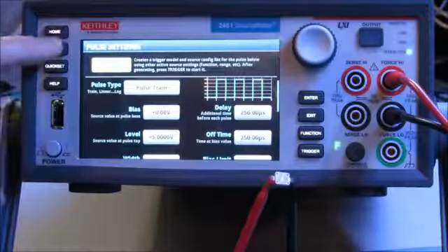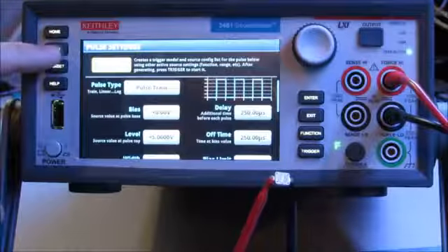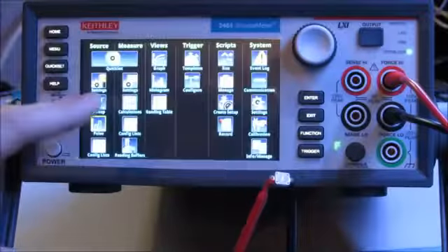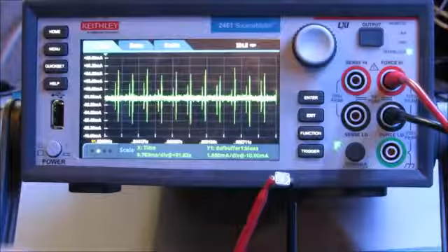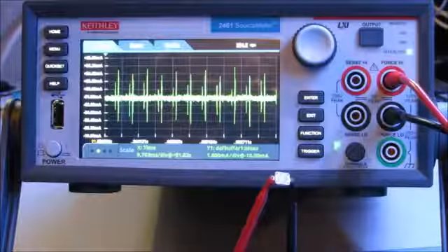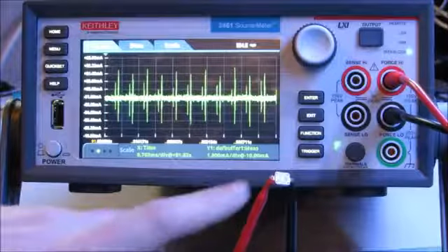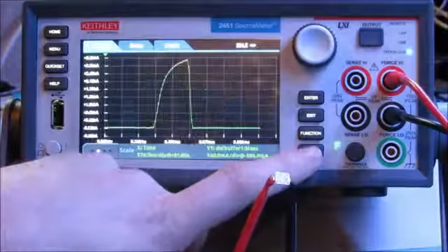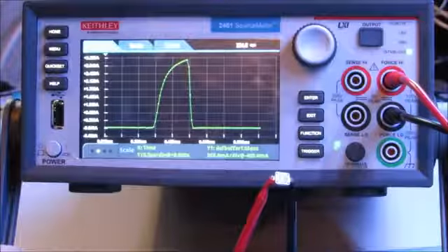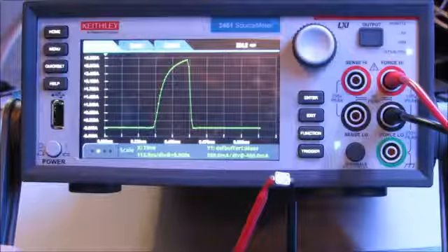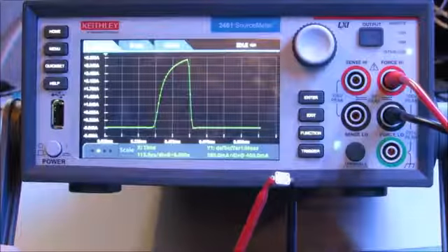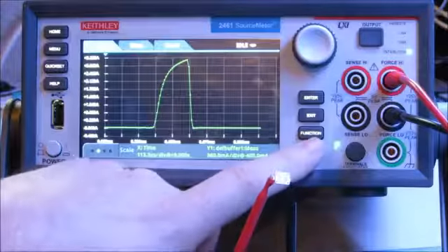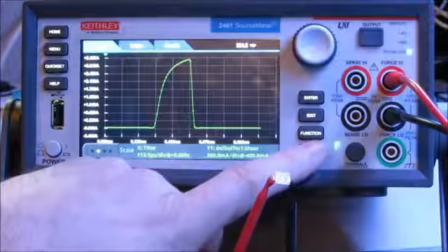So that I can view the graphing capability of the digitizer, I'm going to hit menu, go to views and view graph. Okay, I haven't hit the trigger button to start the test, but let's do that right now. When I hit trigger, you saw the LED flash, and there is the measured current pulse at 100,000 readings per second. I can do it again and get the same results.